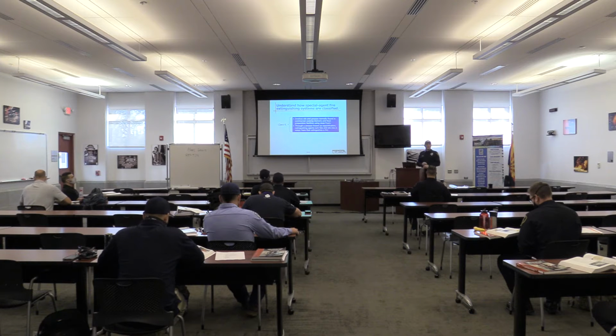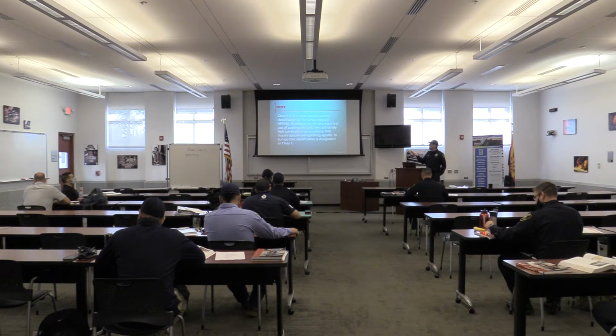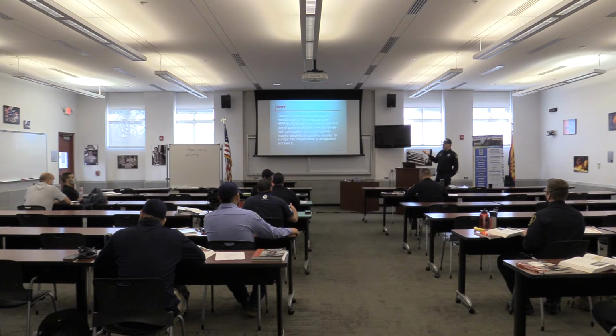Class K fires would be basically kitchen fires where you've got animal and vegetable fats that burn. So your fryers and even just the grease coming off your hamburgers as you cook them. So you're almost exclusively going to see Class K systems in commercial kitchens. You're not going to see them typically anywhere else. And we don't worry about that note, other than the Europeans seem to do things more sensibly. They just went from D to E, and we jumped to K. But K stands for kitchen, just so you know. It's a Class K, just so people can remember what a Class K is for.